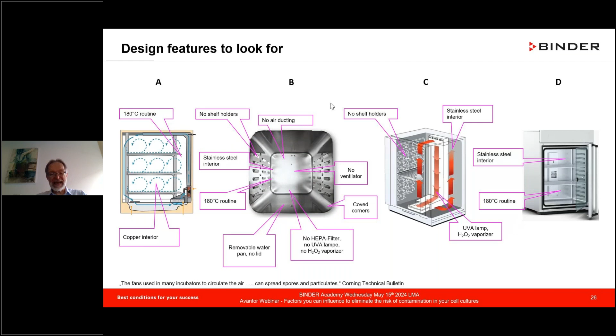And really appreciate that comment from Corning Technical Bulletin, where they actually do state the fans used in many incubators do circulate the air, can spread spores and particulates, and that's the bottom line. So that is something you should have on your radar screen. Typical decontamination methods, here you go, 4 of them. We have the HEPA filter. Must be removed before 180° C routine, must be changed every 6 months. It is a collector. That's where I have a little stomach ache right here, right next to my cell cultures, but that is a decision everybody has to make for themselves. And you have rather large surfaces due to that air duct system.